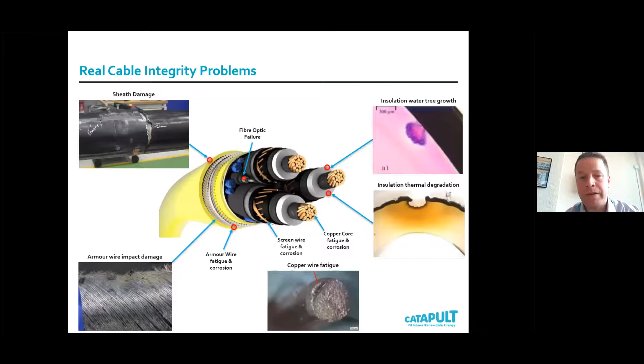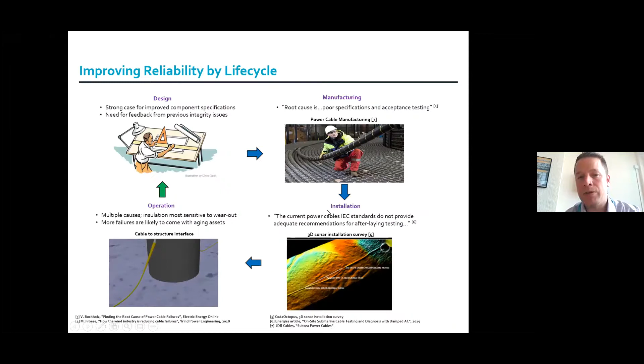And oil and gas umbilicals, there's a lot of experience of power cables, so we can learn a lot about those to find out what we're expecting to happen. And the data, although it's quite sparse from oil and gas umbilicals, is that the cables are certainly the weakest part, the part that's most likely to fail. So that's the area you need to look at in your fatigue and upper assessments. Manufacturing, we do see quite a lot of issues, and it is being improved, but there's more work needed to make sure we can produce particularly cable cores of good quality. Installation is the cause of most of the static fixed cable failures, so we expect that to still be the case with dynamic cables. So control of the installation process and planning, quality assurance is the key part there. And then operation, well, what we expect to cause failure I've discussed, but this is all speculative, we just don't have the data to say yet. But certainly we feel that fatigue and insulation degradation is the most likely cause of long-term failure.